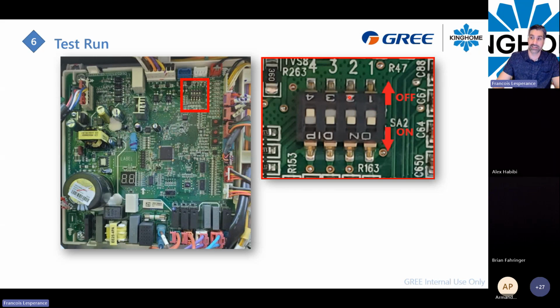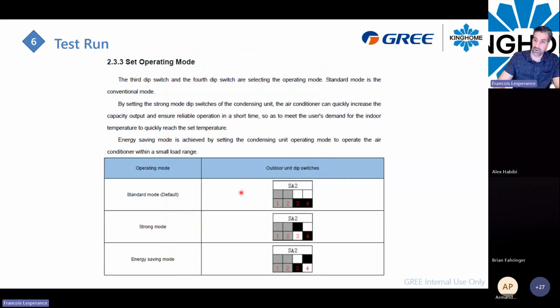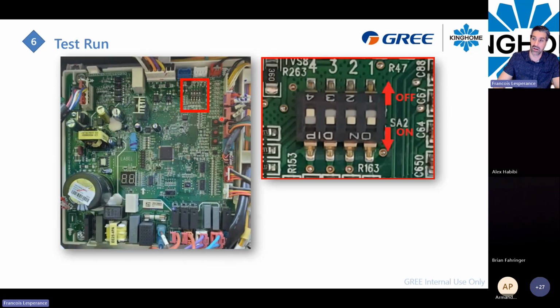The dip switch number 2 is my defrost. By default it's on, so my defrost is a standard defrost. Numbers 3 and 4 are the capacity mode. If they were off, I would be standard. I am on, off, or off, on. In that case, I am on, off. So this means this system is a 3-ton unit, standard defrost, and strong mode. This is what it looks like. If they were off, it would be standard operation. But now, because it's on, off, strong mode is active.